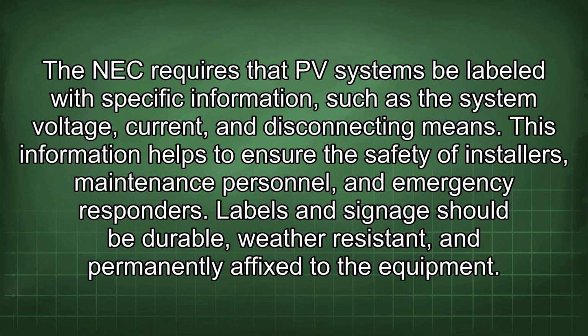The NEC requires that PV systems be labeled with specific information such as the system voltage, current, and disconnecting means. This information helps to ensure the safety of installers, maintenance personnel, and emergency responders. Labels and signage should be durable, weather-resistant, and permanently affixed to the equipment.